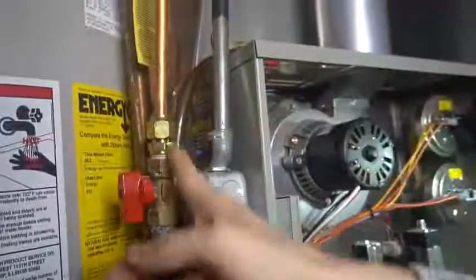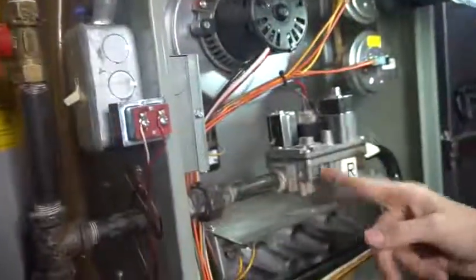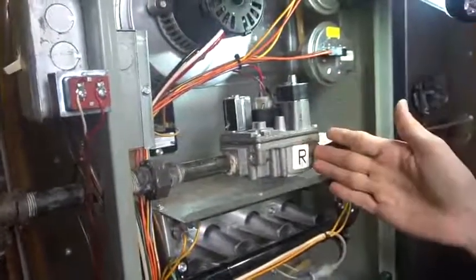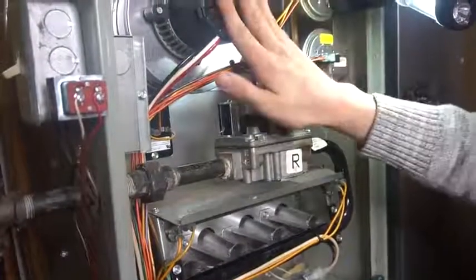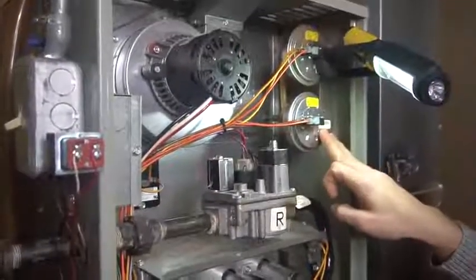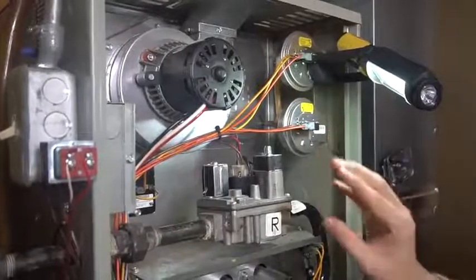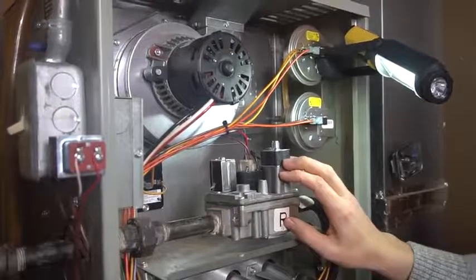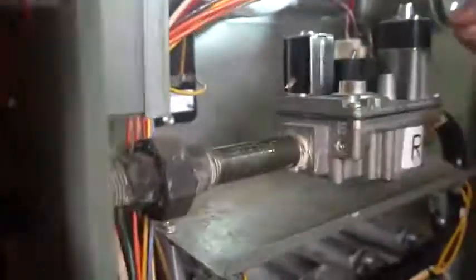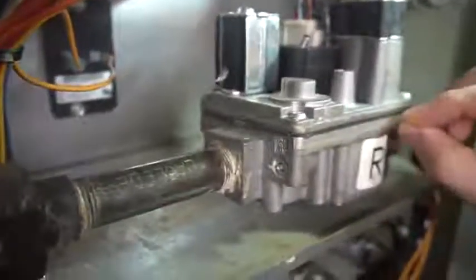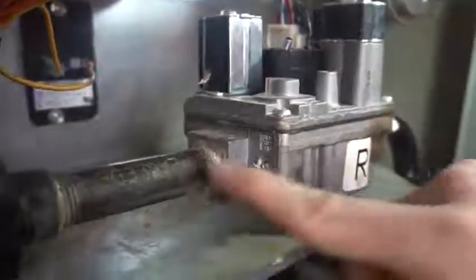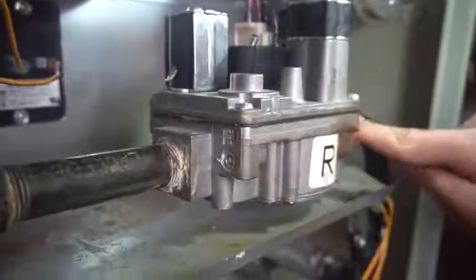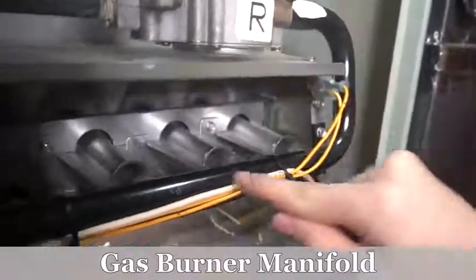But anyways, the gas comes in through the gas pipe right here, goes into the gas valve, and it stops right here. So the way it works is the inducer motor turns on, the pressure switch closes, then the igniter starts to glow, and that's when the control board will tell the gas valve to open. Once the control board tells the gas valve to open, this valve inside will open up and allow the natural gas through. Then this piece right here is called the gas manifold, this black J-shaped piece.